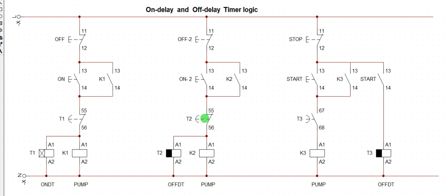Now this contact will change state two times. The first time is when the coil is energized. The second time is when the counting time elapses. So that is the two times this contact makes a change. So these two logic will not function where you use two different timer functions. Now if you want to use off delay, look at the logic here.